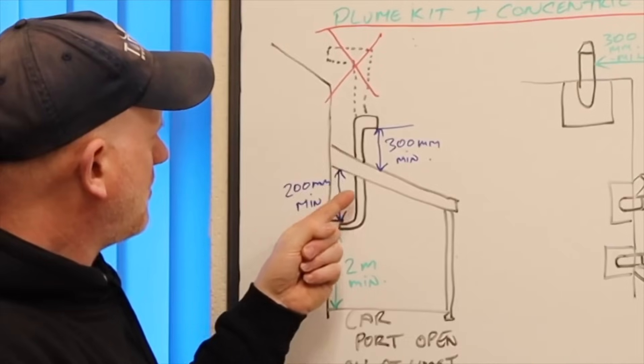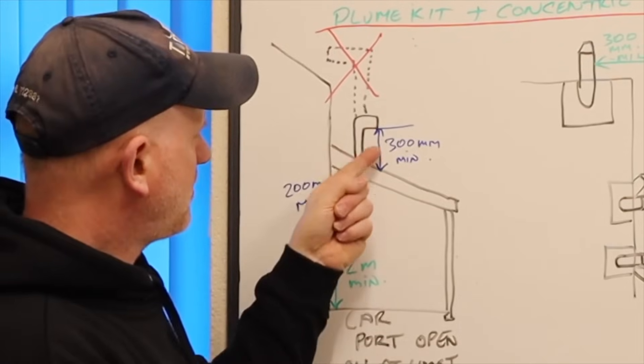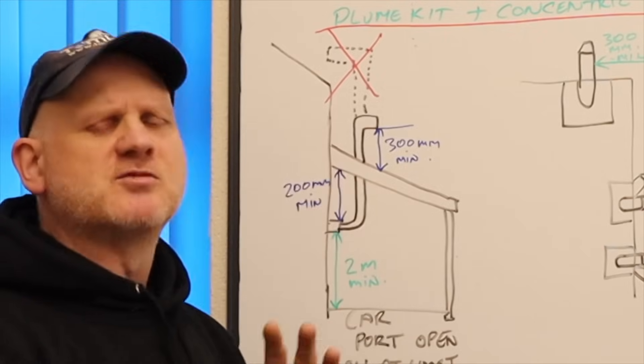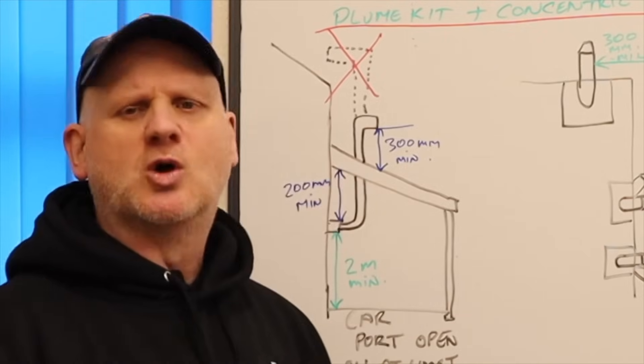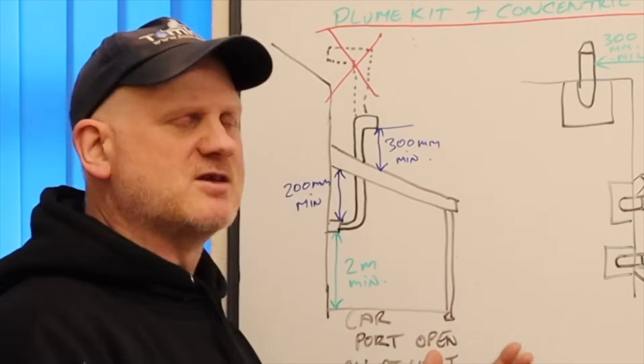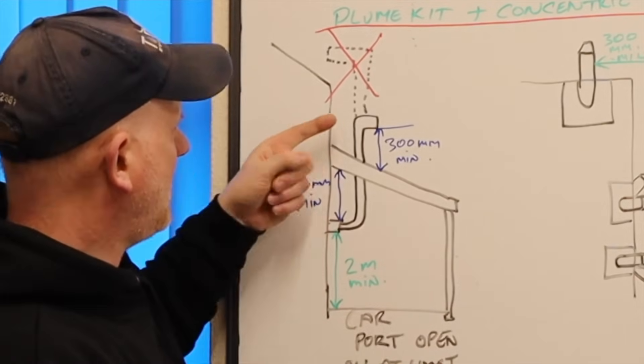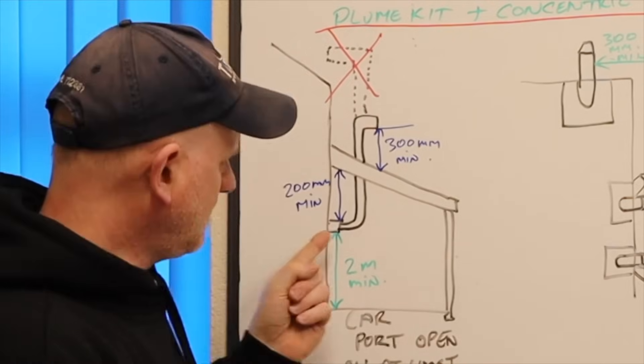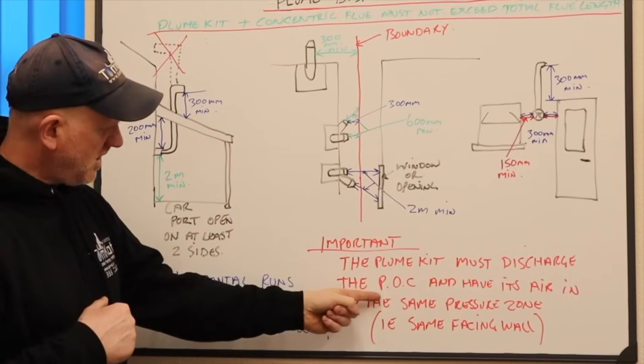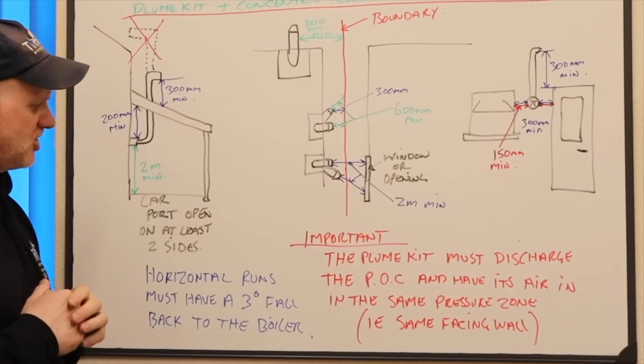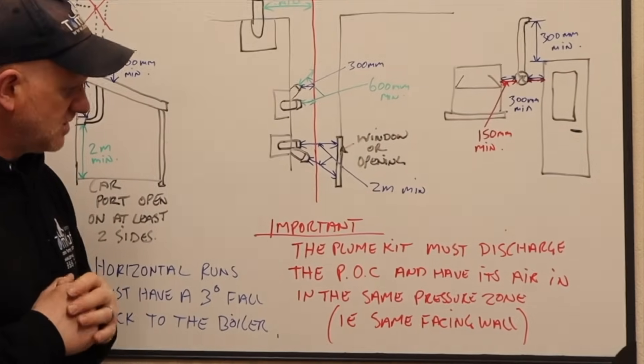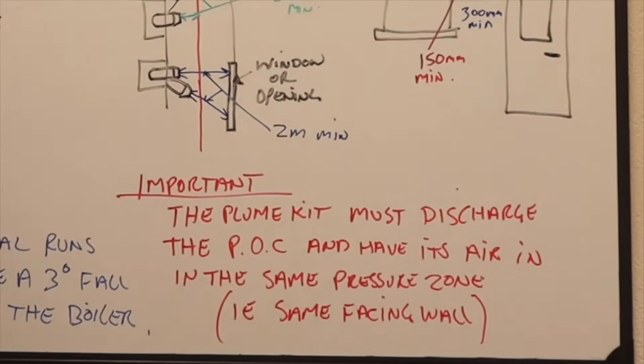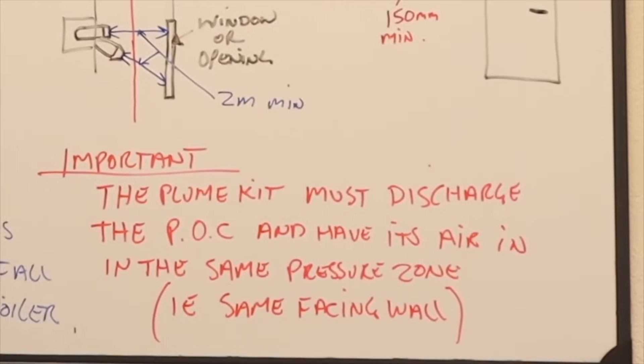So, when we come above the roof, we must be 300mm above the pitch of the roof, like we would be from ground level to stop snow and leaves and rain bouncing back in there. The other major thing is, it has to face the same way as the air inlet. Because the plume kit must discharge its products of combustion and have its air in, in the same pressure zone. That basically means facing the same way on the wall.